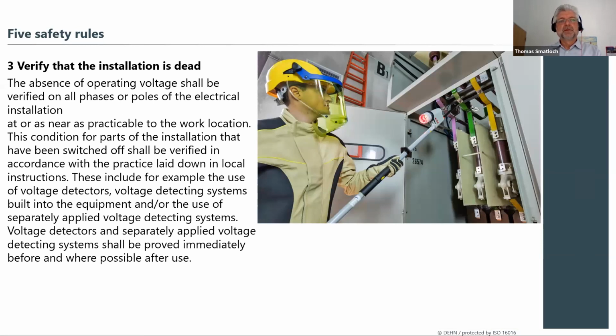Good. Safety rule number 3 is about verifying that the installation is dead. So the worker here in this picture shows an instrument, which is a voltage tester, a mobile voltage tester. And this is not a measuring instrument, by the way. You don't measure the voltage in this case. He only gets the information if voltage is present or if it is switched off. So this is important for him, just to have this information, not the exact value of a certain voltage. So this is shown here.